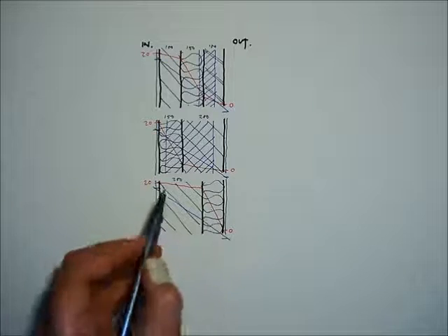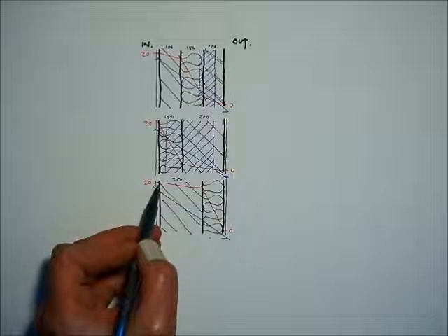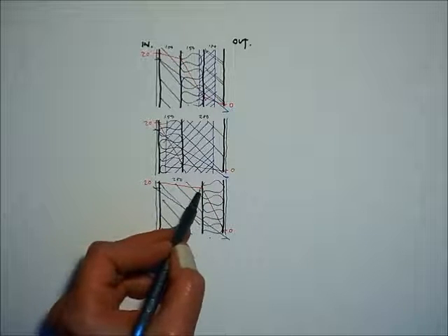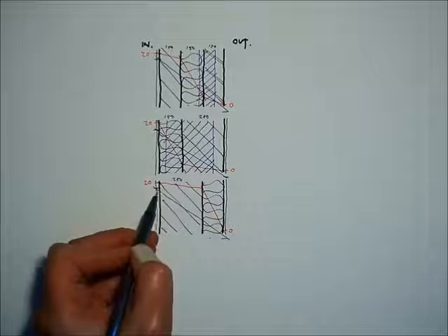Moving the insulation to the outside makes the temperature gradient push away from the dew point gradient and no condensation risk occurs.